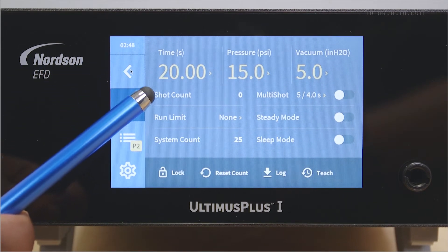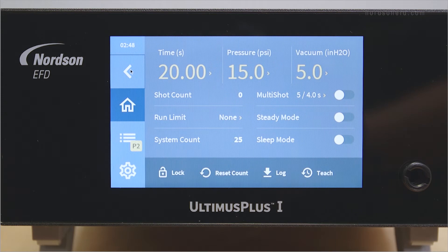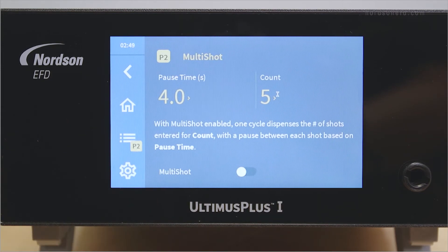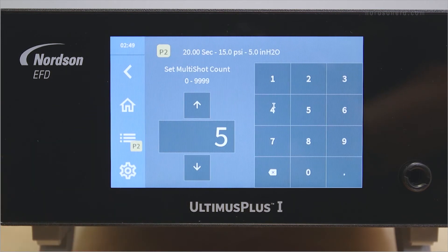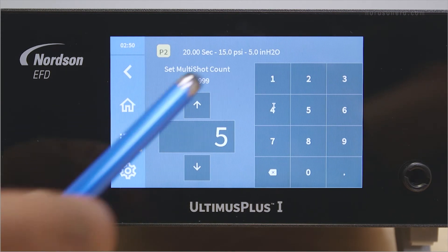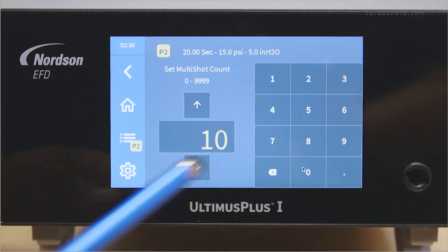This will let you know how many dispense cycles have been performed with your Ultimus Plus. The Ultimus Plus has a multi-shot functionality that allows you to perform multiple dispenses with one cycle initiation. To change multi-shot settings, press the multi-shot section on the touch screen. Press the count section — this is the number of shots in the dispense cycle. Enter a value for count and wait for the unit to accept it.